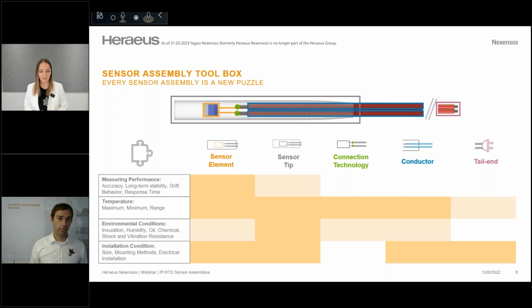Let's get to the next requirement, the temperature. We talk here about the maximum operating temperature, the minimum, and the temperature range. And actually, all different component parts of the sensor assembly need to be matched to the application's temperature. So we need to choose the right sensor element. We need to choose the right materials for the sensor tip. Also, when we talk about the connection technology, for example, a soft soldering connection would not withstand really high temperatures. And depending on where the sensor assembly is installed, the conductor and the tail end also need to be adapted in terms of the temperature.